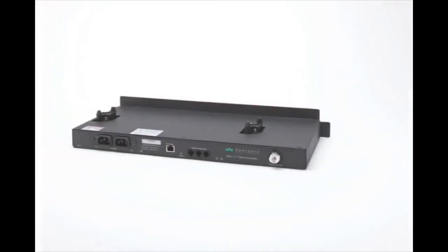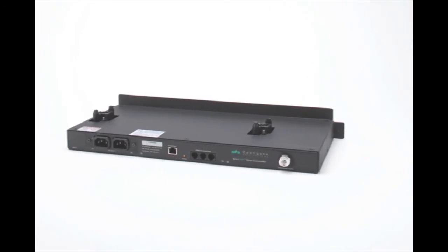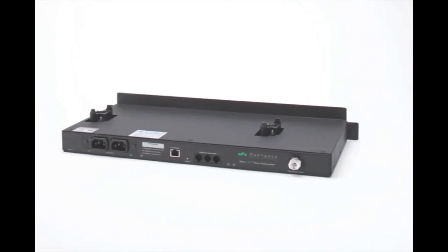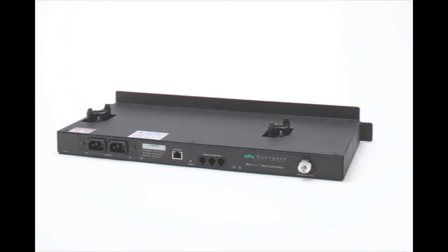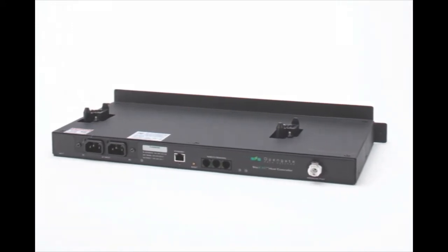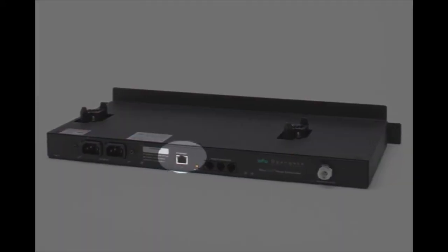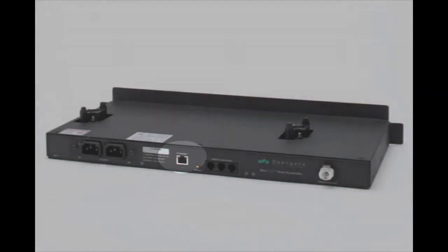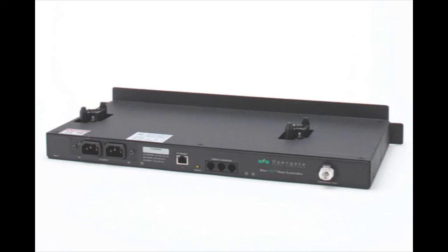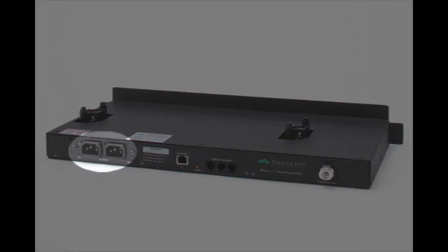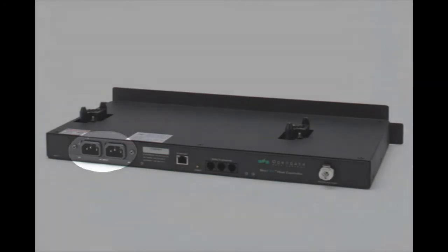At its core, CoolCirc-IT's networking module is used to control the system. Each module has software pre-installed, so there is nothing to load on a server. The module allows IP access via Ethernet, so users can perform real-time cooling capacity assessments to effectively manage equipment adds, moves, and changes. Email alerts are sent when conditions fall outside of the user-defined SNMP trap thresholds for temperature, humidity, and capacity. The network module comes with dual power inputs for redundancy as well.